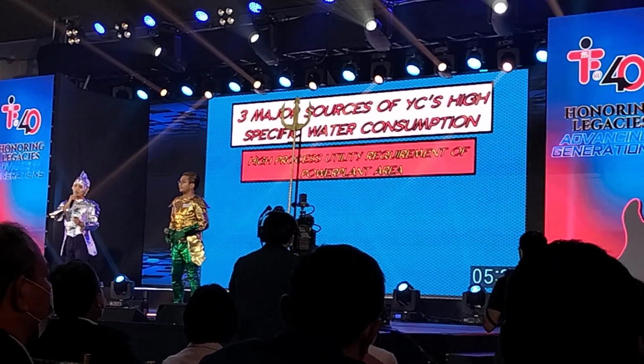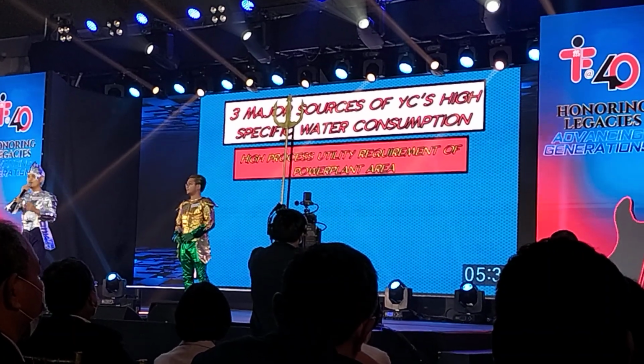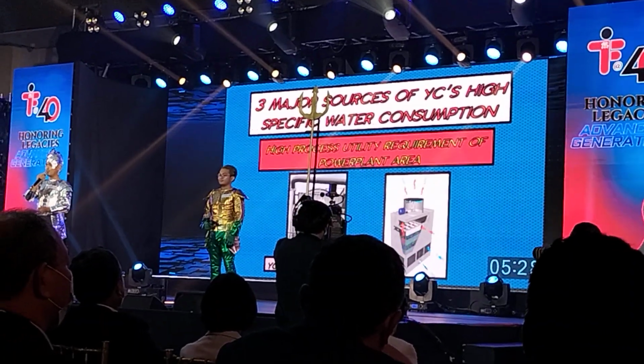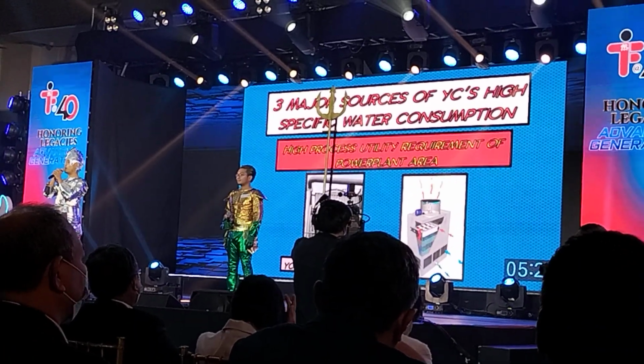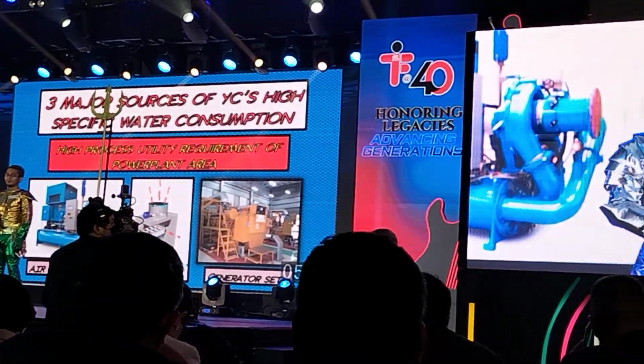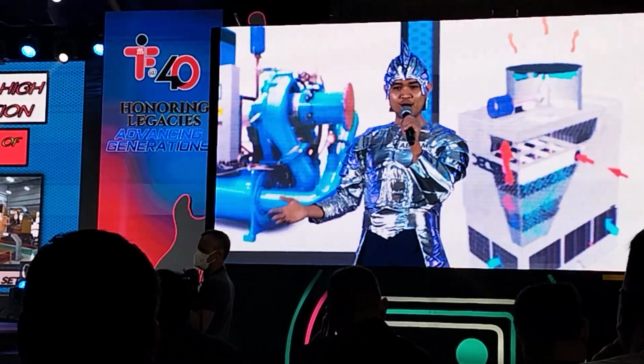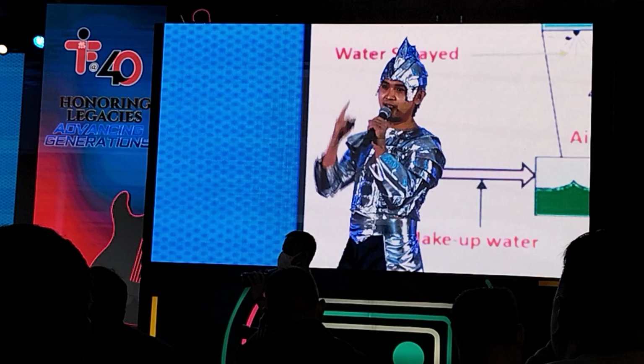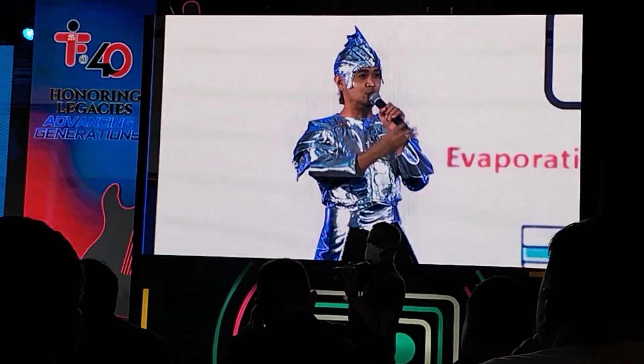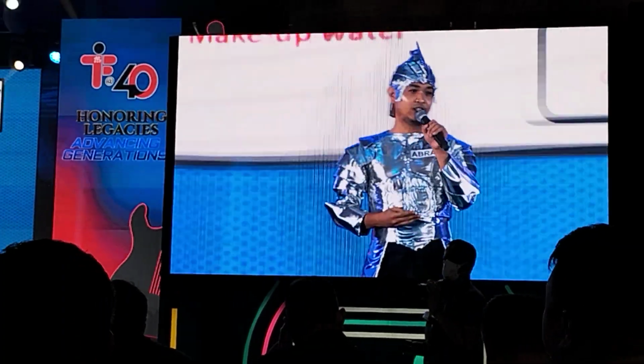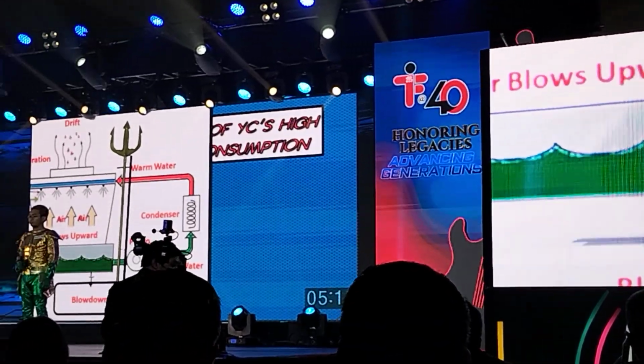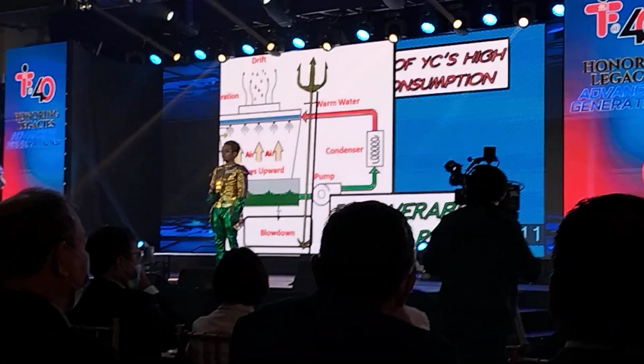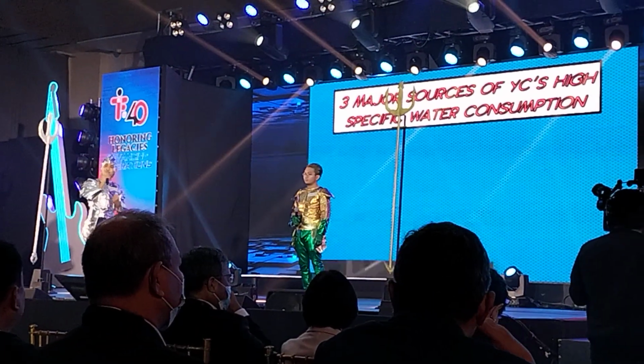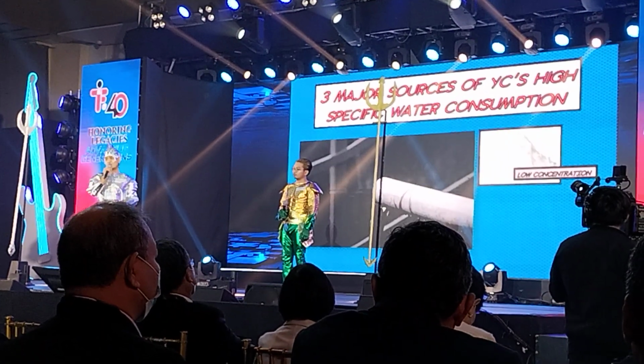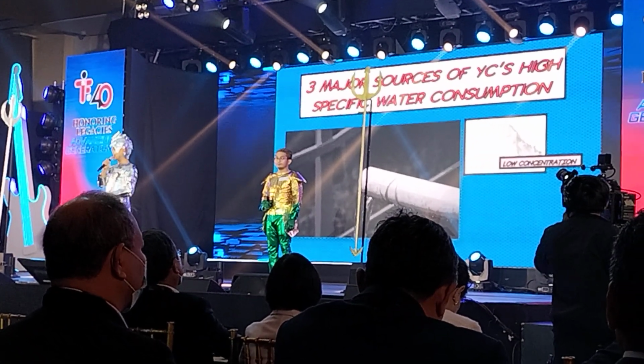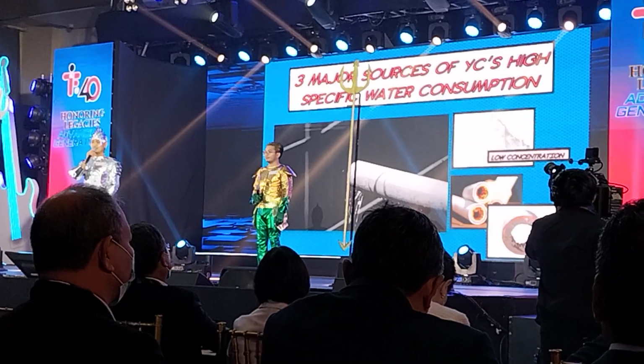Another identified contributor is the YC cooling towers. These are specialized heat exchangers responsible for the cooling water system of air compressors and generator sets. In general, cooling towers have three types of losses: evaporative, drift, and blowdown. Of the three identified losses, only blowdown is recoverable and can be reused. It is the amount of water necessary to be removed from the system in order to maintain the low concentration of minerals and prevent scaling and fouling through pipes and fittings.